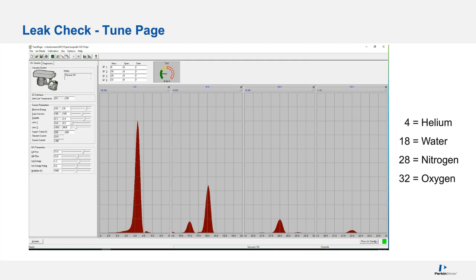Perhaps the filters are going bad, or the leak is before the filter, or your nitrogen purge valve. Because we can vent our mass spec to UHP nitrogen instead of lab air, that valve could be leaking. So before I go crazy looking for a leak, I make sure that the leak is coming from air, because it is the oxygen doing the damage, not the nitrogen. Nitrogen being around is not going to cause damage. It may change your chromatography a little bit, but it's not going to hurt anything. So you could still be productive, is what I'm getting at. So I always make sure it is air that I'm seeing.